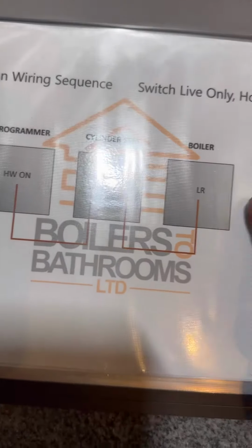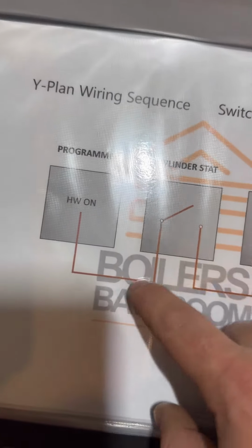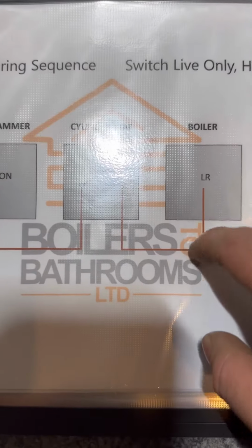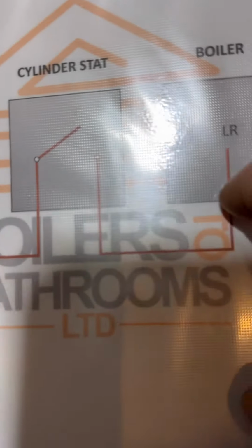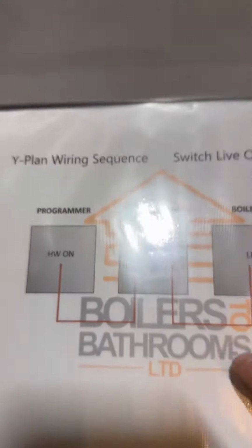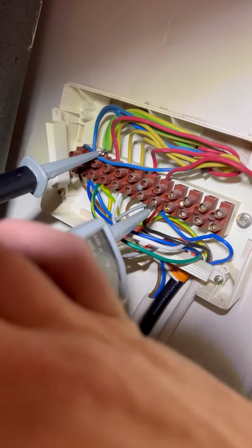Right, for hot water on a Y-plan, it goes from the programmer to the cylinder stat, and then it goes to the boiler on orange. So it doesn't even go to the Y-plan valve. All it does is take power off grey, which opens up the port. So we can check that now. 240 on orange, switch live, boiler's firing for hot water.